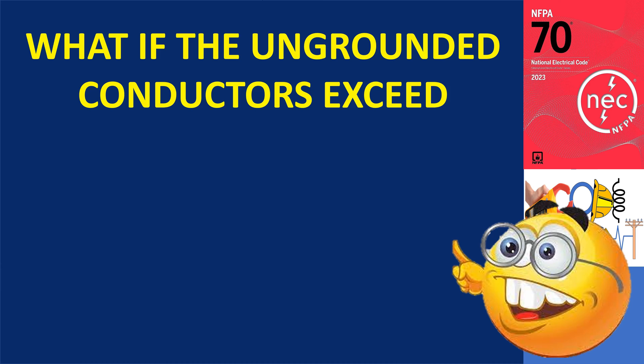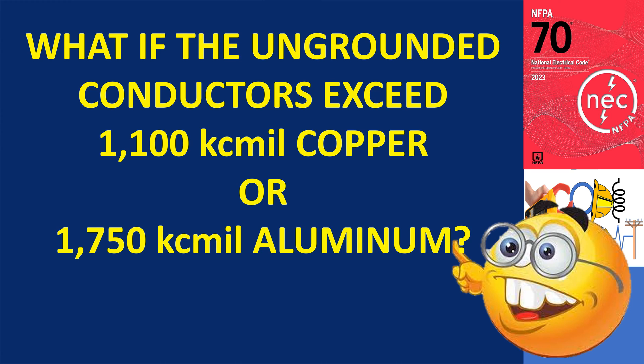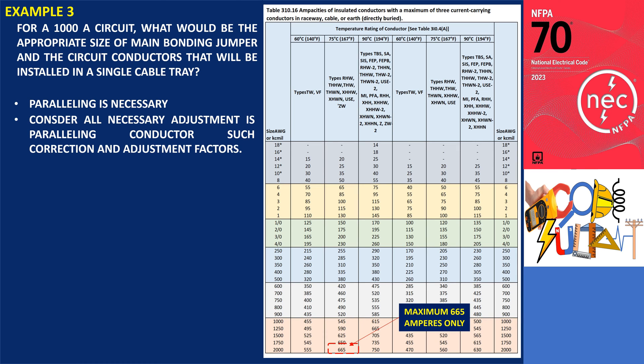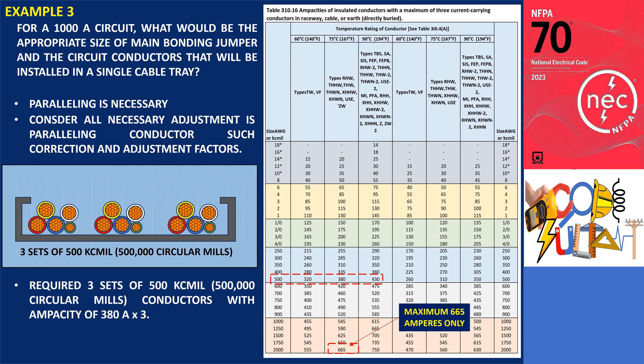Let's consider a scenario where the ungrounded conductors exceed 1,100 kcmil copper or 1,750 kcmil aluminum. Consider a 1,000 amp circuit to be installed in a cable tray. According to table 310.16 for ampacity, there is no single conductor available for that ampacity, so paralleling of conductors will be necessary, taking into account correction and adjustment factors. To accommodate the 1,000 amps, we would require 3 sets of 500 kcmil conductors, resulting in a total combined circular mil area of 1,500,000 (1,500 kcmil).